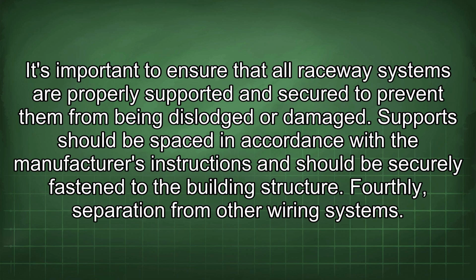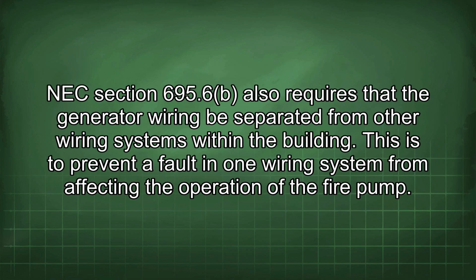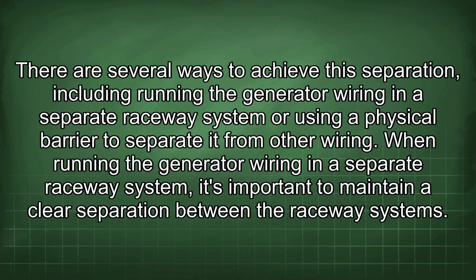Fourthly, separation from other wiring systems. NEC section 695.6 also requires that the generator wiring be separated from other wiring systems within the building. This is to prevent a fault in one wiring system from affecting the operation of the fire pump. There are several ways to achieve this separation, including running the generator wiring in a separate raceway system or using a physical barrier to separate it from other wiring.